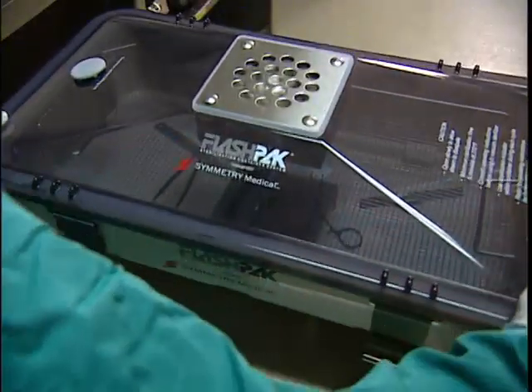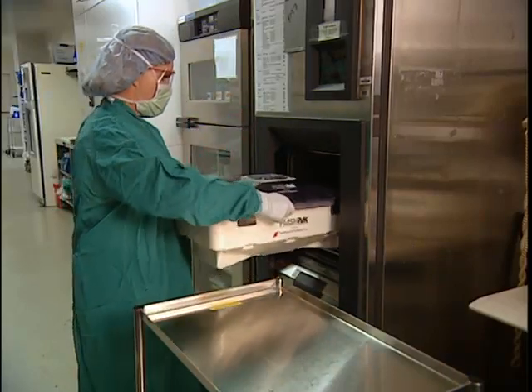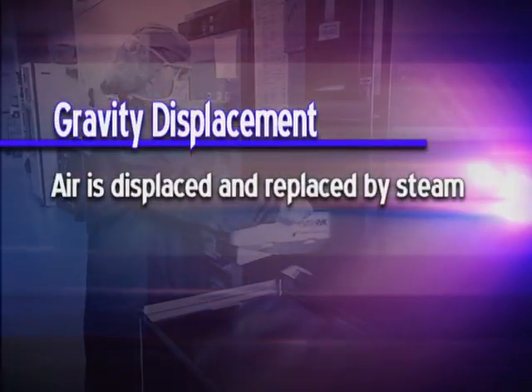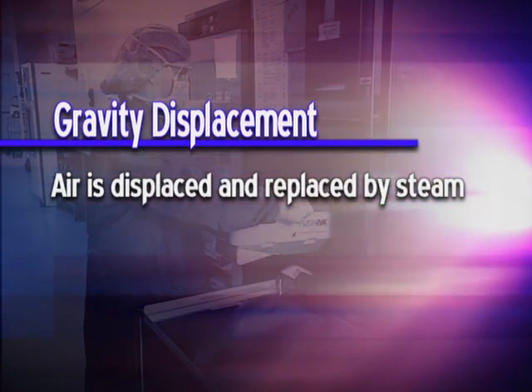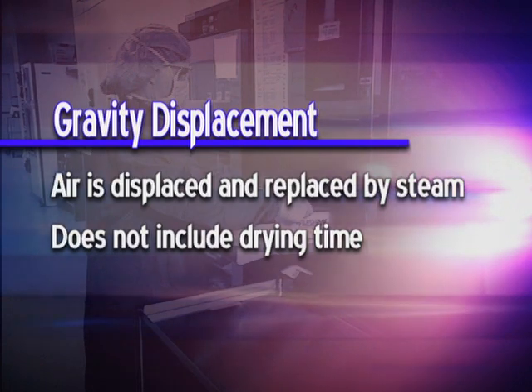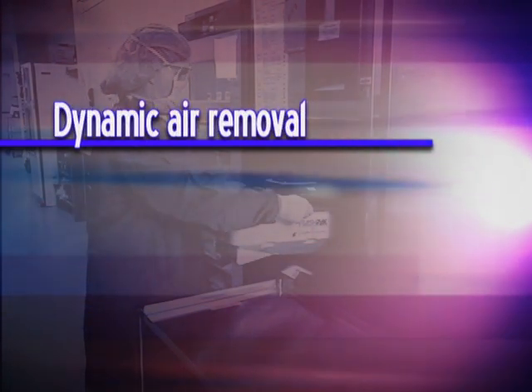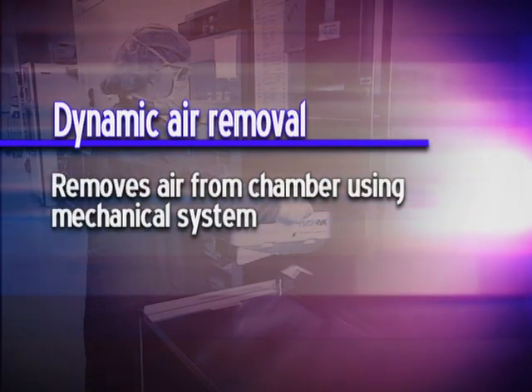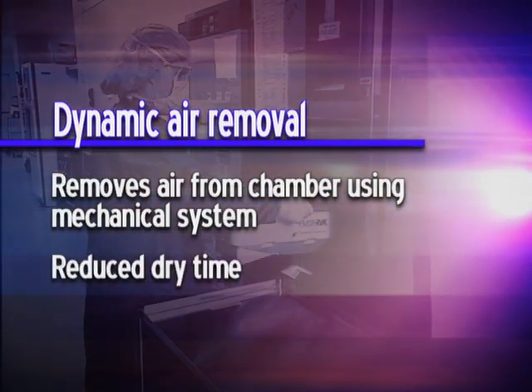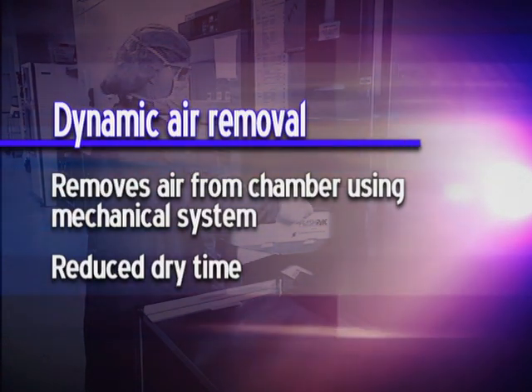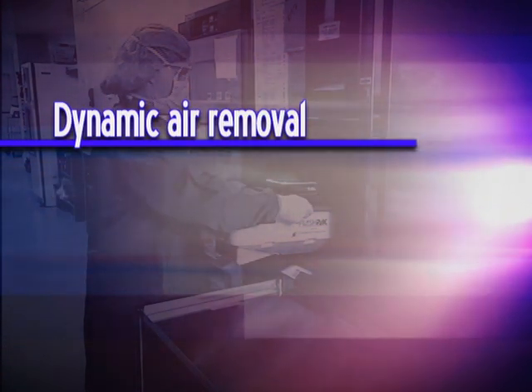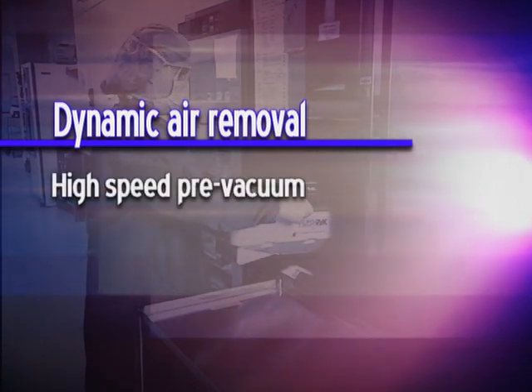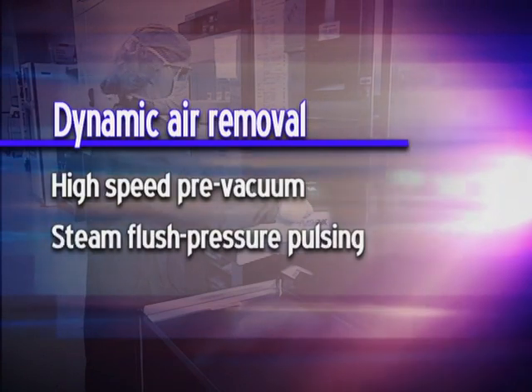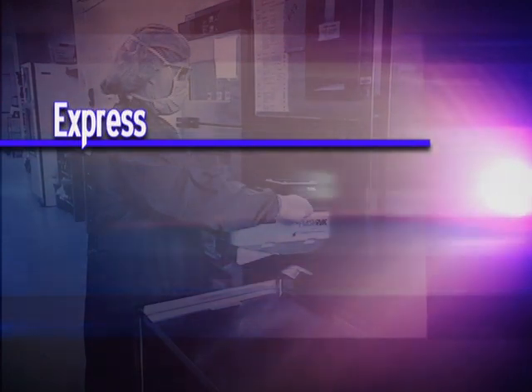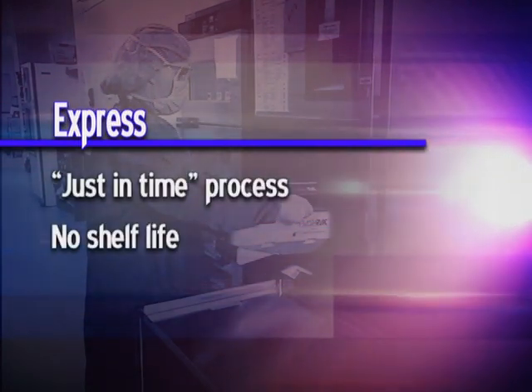There are three types of immediate use steam sterilization. Gravity displacement uses gravity in the conditioning phase to displace air and replace with steam. It does not typically include a drying time. Dynamic air removal sterilizers remove air from the chamber using a mechanical system. When used for immediate use steam sterilization, drying time is reduced. The two types of dynamic air removal sterilizers include high-speed pre-vacuum and steam flush pressure pulsing process. The third type of immediate use steam sterilization is the express, a just-in-time process with no shelf life.